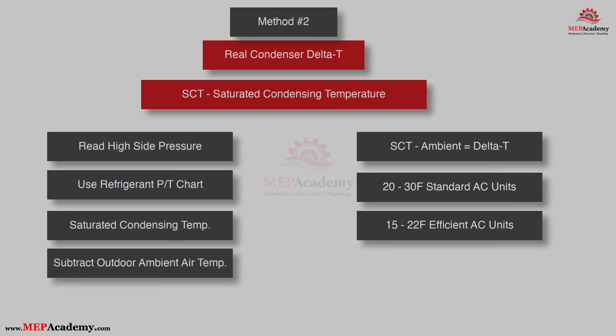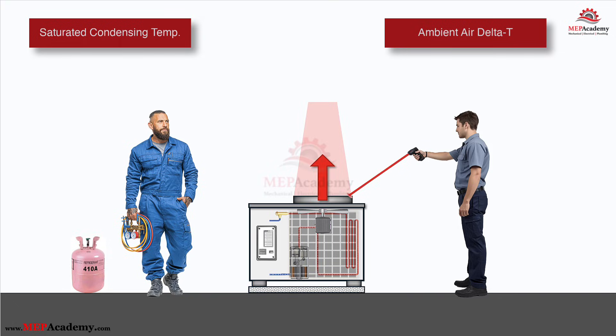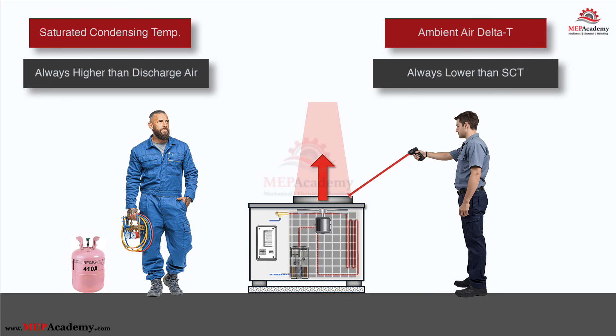So one is fast, one takes a little effort. Which one do you trust? This is where many technicians run into trouble — they try to use the SCT number to estimate airside delta T. But SCT is always higher than the air discharge temperature because the refrigerant is hotter than the air being blown off the unit. The two measurements are related but they're not interchangeable, and substituting one for the other will lead to incorrect conclusions about airflow, coil cleanliness, or charge. Air side delta T does not equal SCT. They are two different measurements serving two different diagnostic purposes.